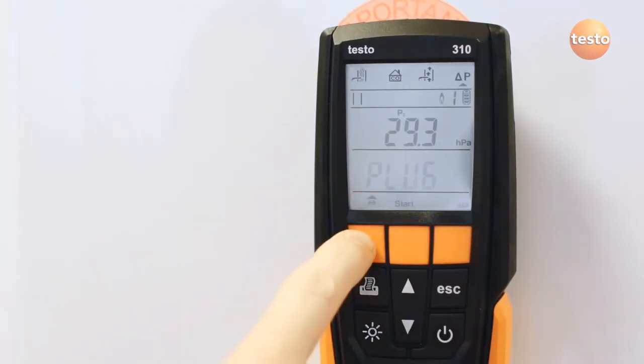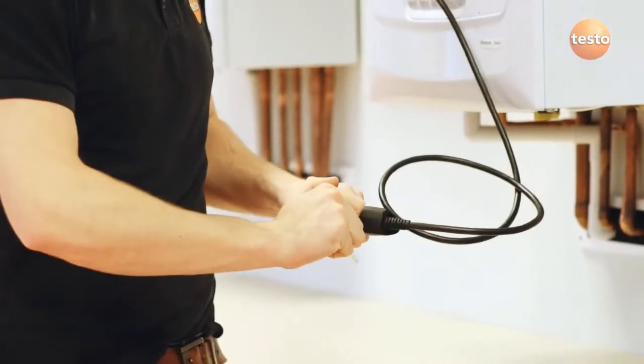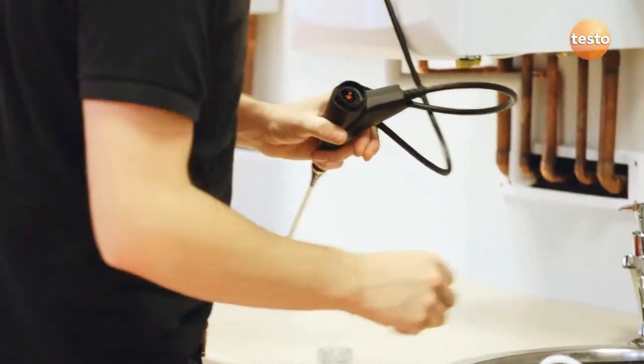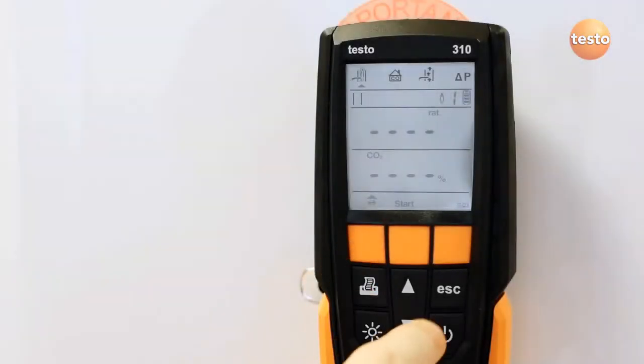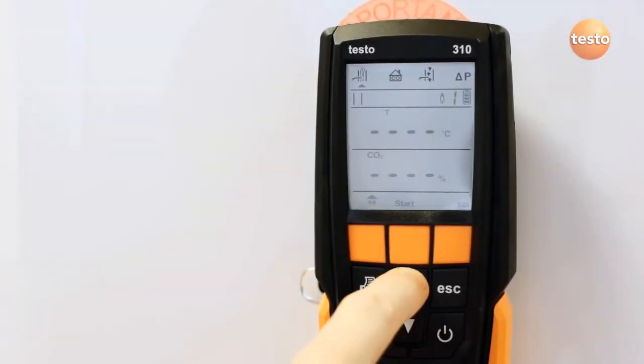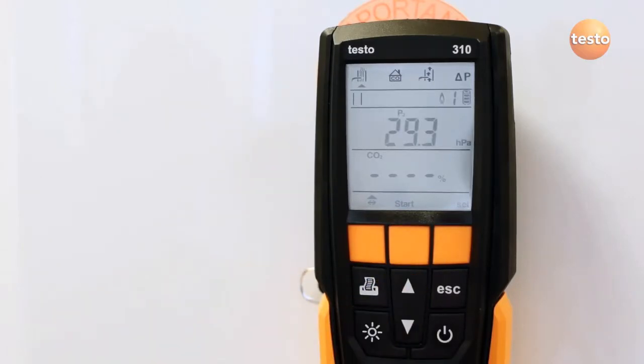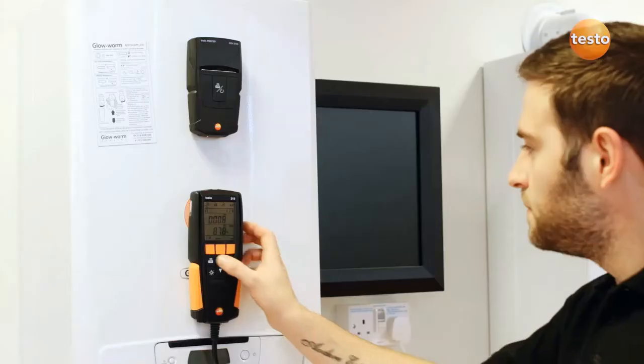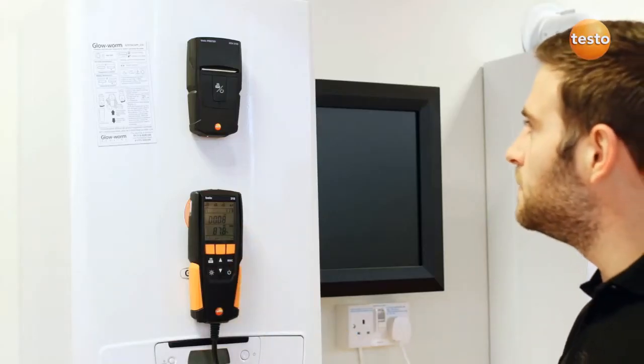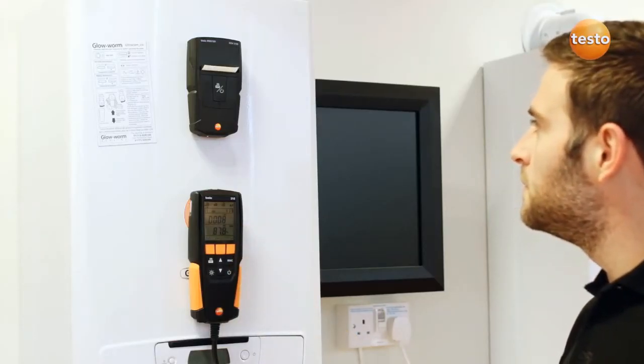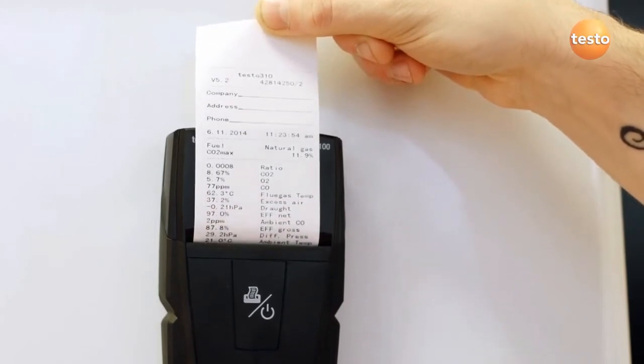When you press stop at the end of the test, the analyzer will remind you to remove the plug and refit the filter in the probe handle. The pressure and draft readings are held in the analyzer as long as it's switched on. The pressure reading is labeled P2 and draft would be stored as P1. Now when the ticket's printed, it will include pressure measurements as well as the associated flue gas readings.